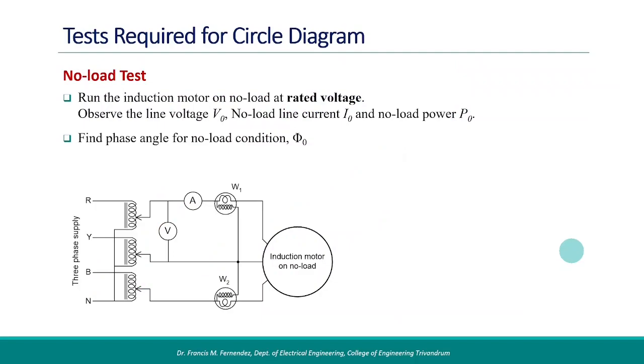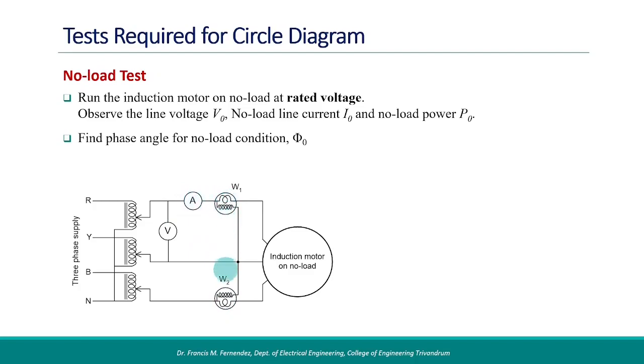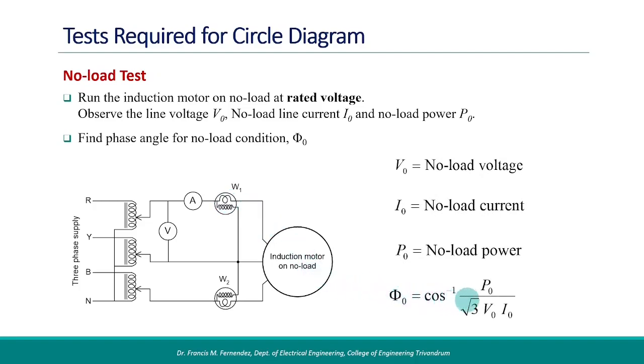For the construction of the circle diagram, we need some test data. First, the no-load test readings. The motor is to be operated at the rated voltage without any load using the circuit diagram shown here. Adjust the auto transformer to obtain rated voltage across the motor terminals and take the readings. We get the no-load voltage V0, the no-load current I0, and the sum of the two watt meter readings gives the no-load power. From these readings, the no-load phase angle phi0 can be calculated using the expression shown here. I0 and phi0 are required for construction of the circle diagram.